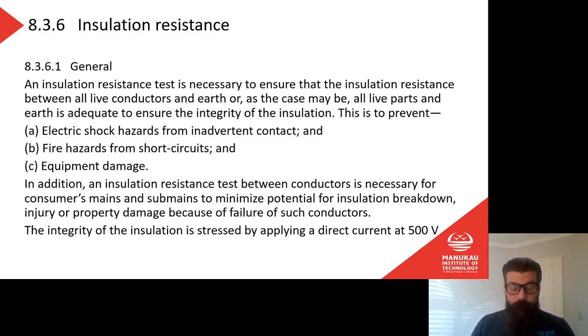And if I had a very slight fault in there, that meter might not pick it up. So what we need to do is put a higher voltage on it. When we connect it to the power supply, for example, it's going to have 230 volts on it, right? We know that. So we at least need to know that the insulation is going to protect us if we've got 230 volts. Well, in fact, we're going to go a step further than that, and we're going to test it with 500 volts.